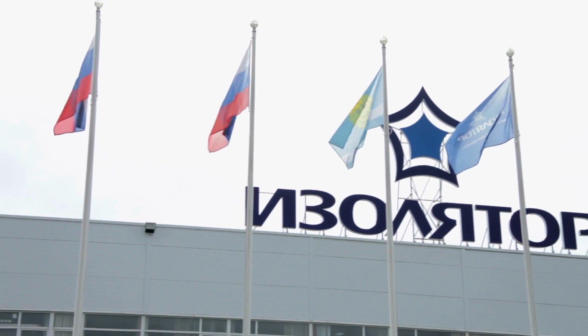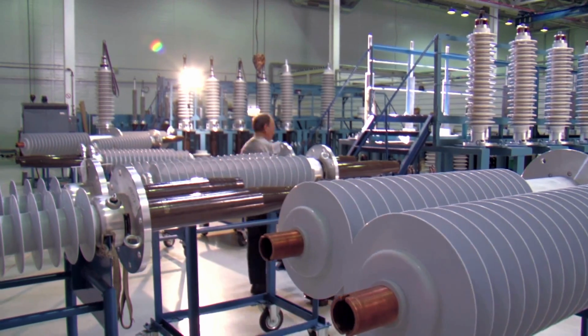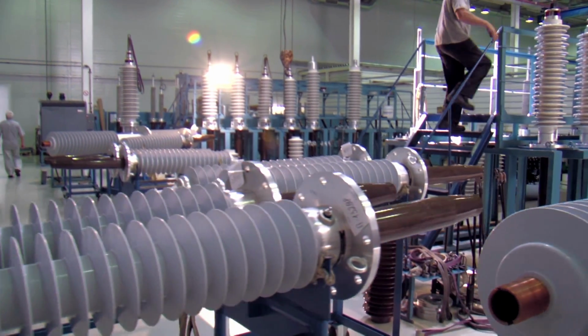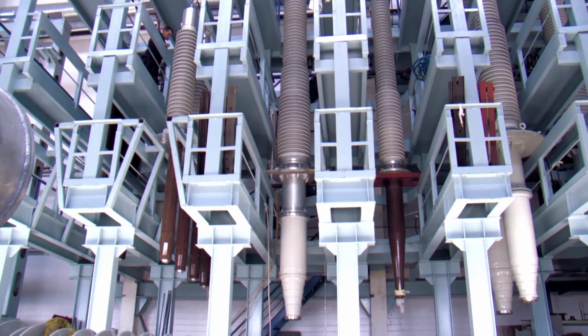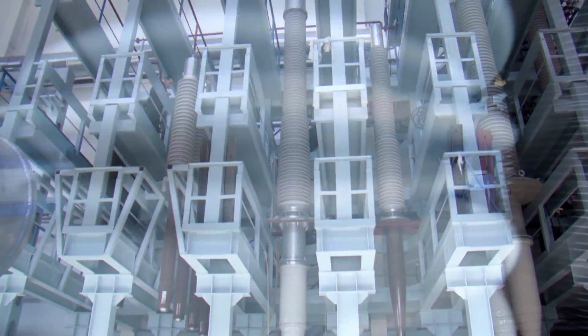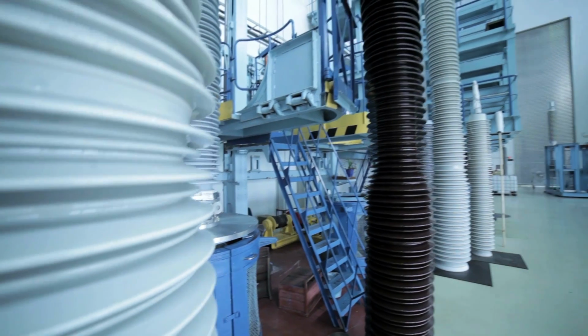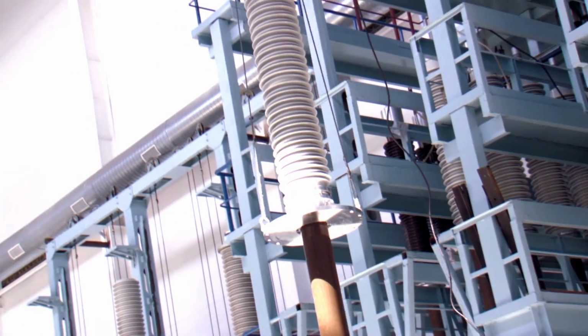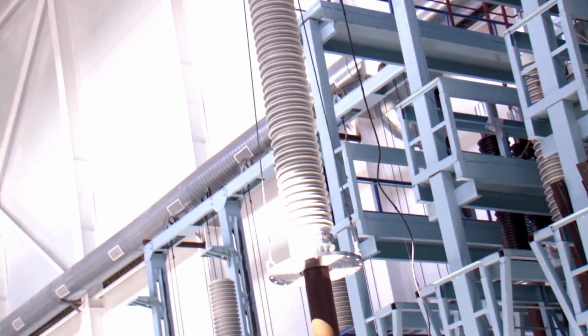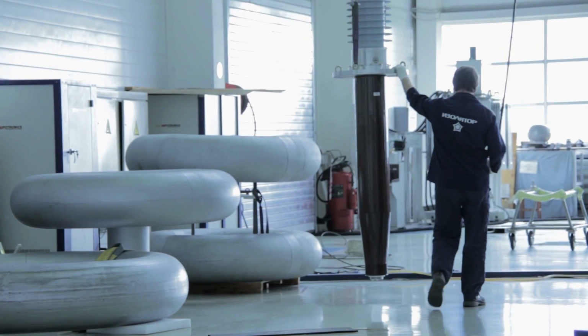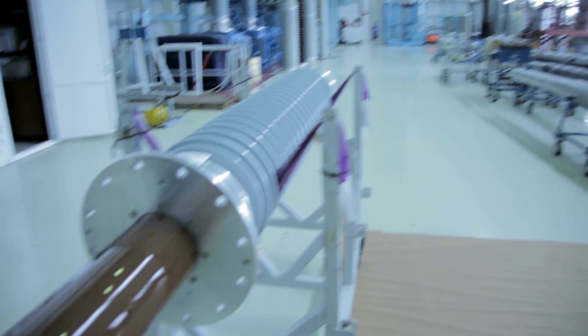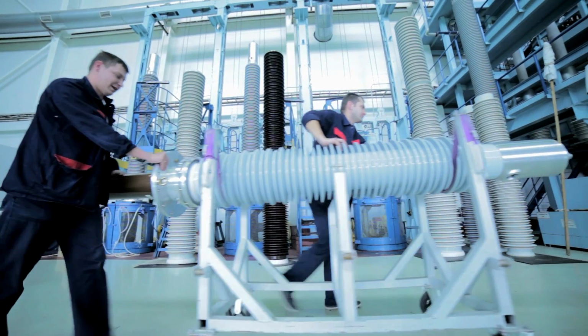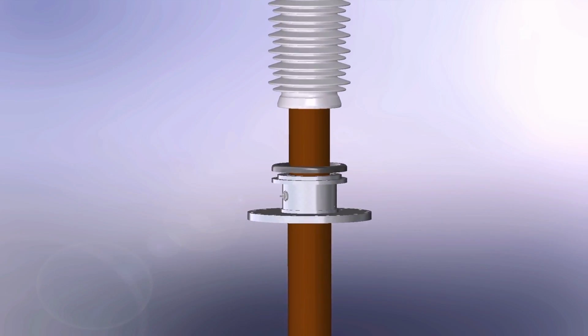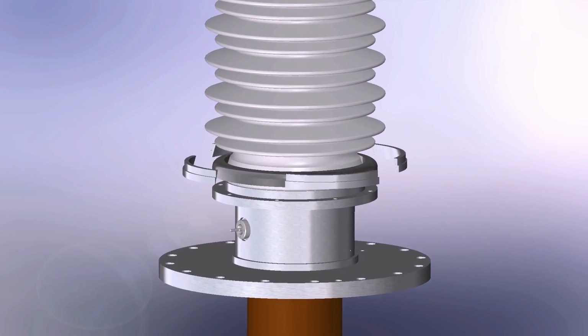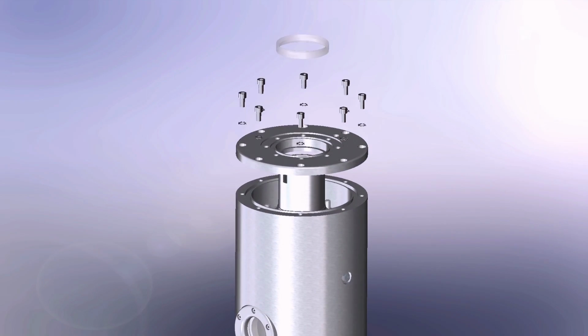Izolyator has successfully developed RIP bushings of up to 800 kV voltages for 15 years. Mass use of RIP bushings in Russia and power industry of other countries shows that the most important stage for a sound bushing operation is its installation in a transformer. Due to RIP insulation design features, this operation has substantial differences from analogs and requires careful study and full compliance with the manufacturer's instructions.